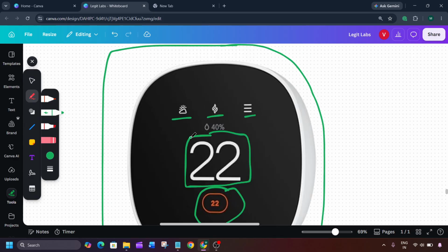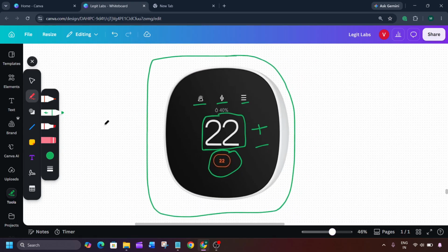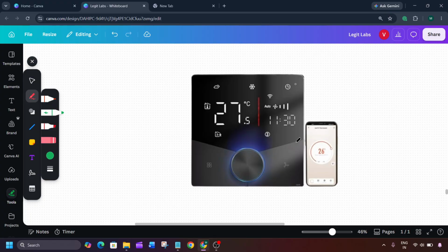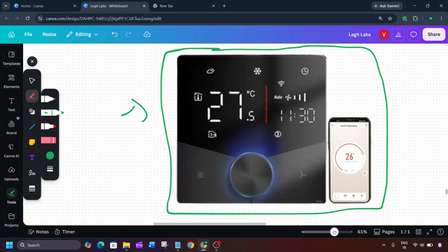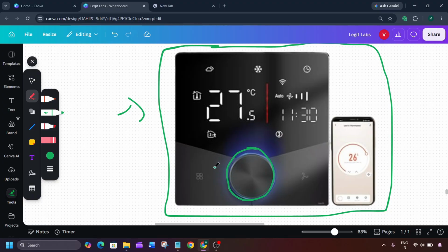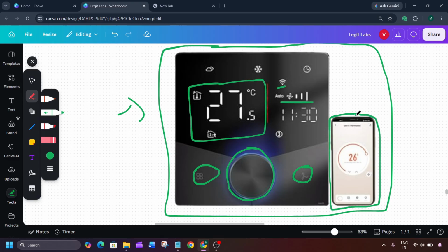This problem is usually caused by incorrect thermostat configuration, reverse HVAC wiring, the system being set to the wrong operating mode, or an installation setting that doesn't match your heating and cooling equipment. In some cases, a recent installation or reset can also cause the thermostat to control the HVAC system incorrectly. These are the steps you can try to fix this.